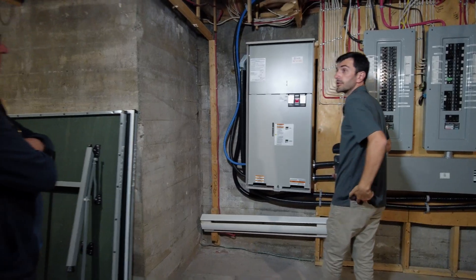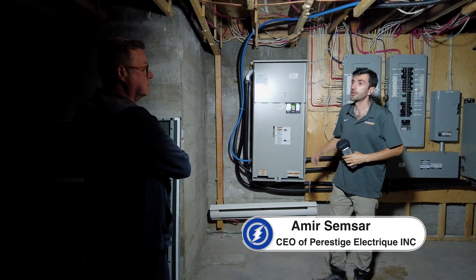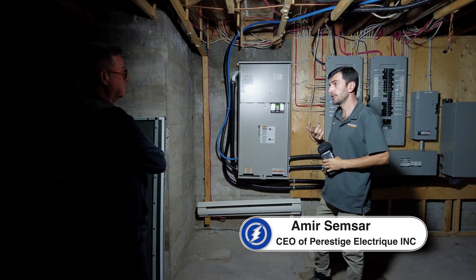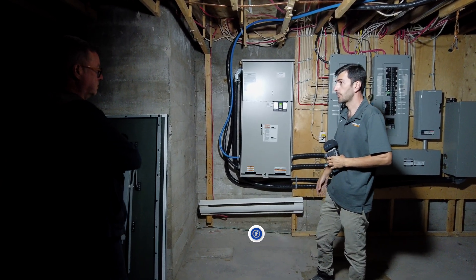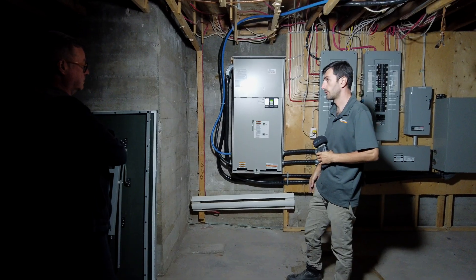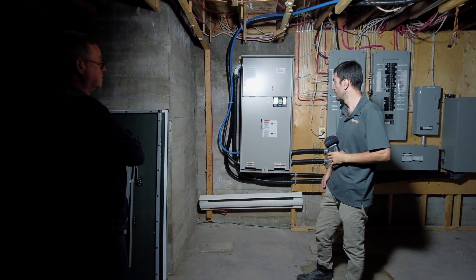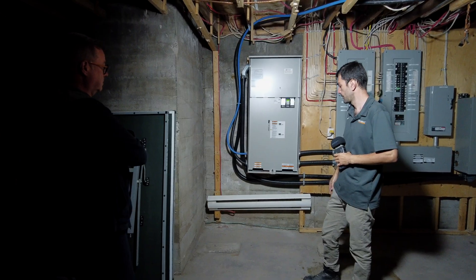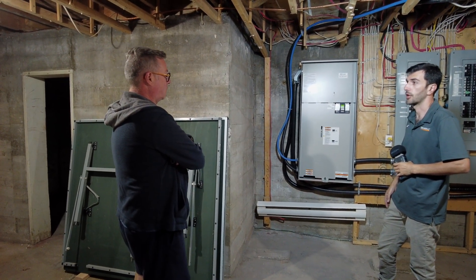You don't need to do this, it's just for the test. I turn off the whole house. Generator is going to start after 5 seconds. Between 10 to 30 seconds it's going to click. It will make a noise, give the power to that. Generator is on. And then it's going to click. Now the whole house is on the generator.